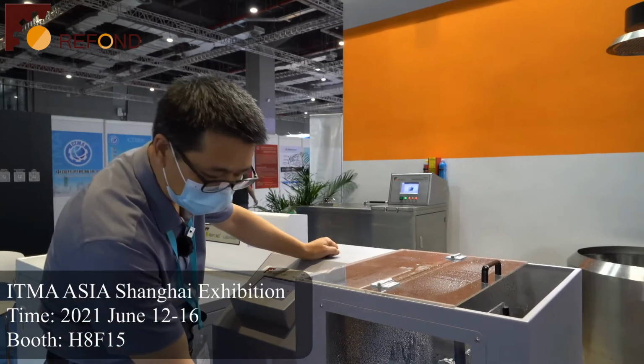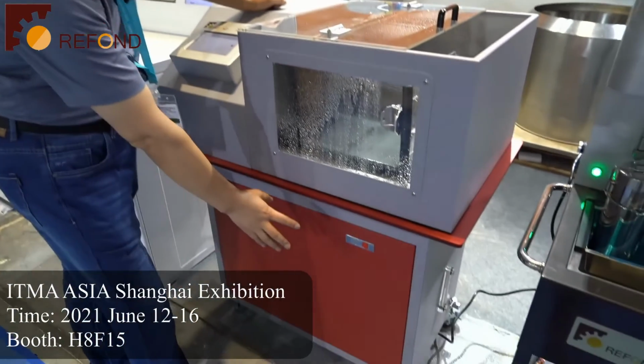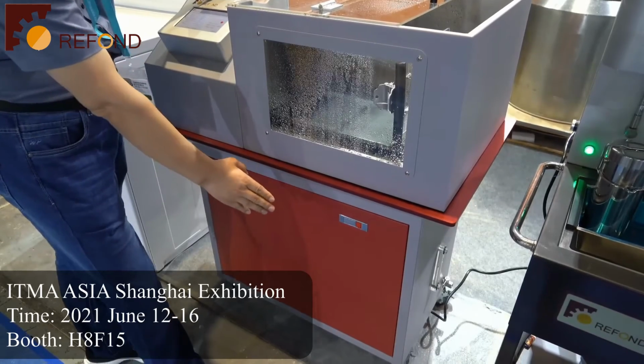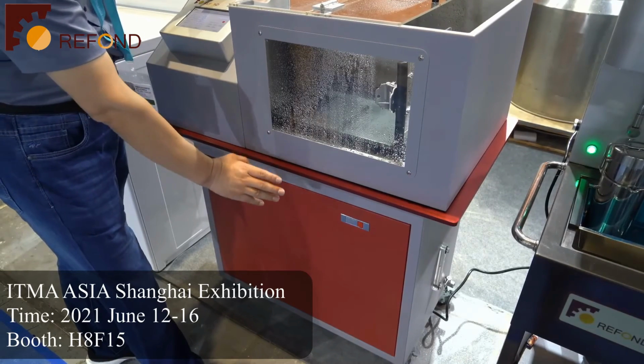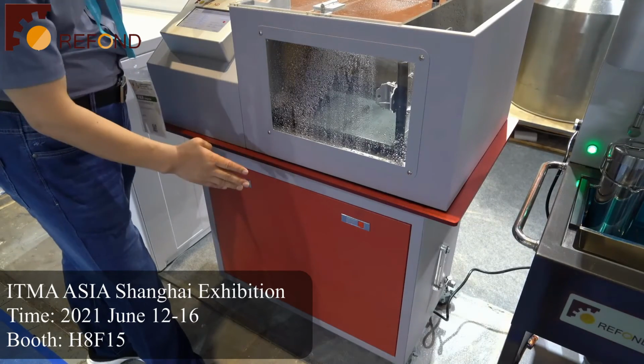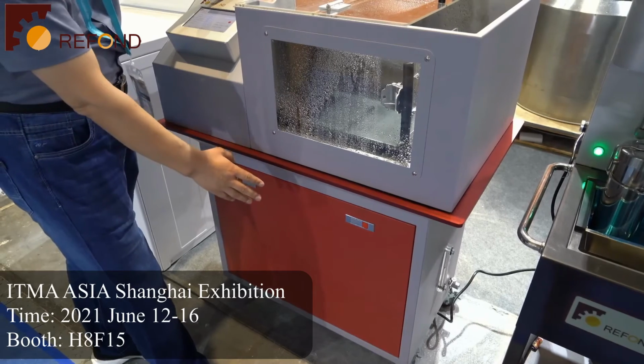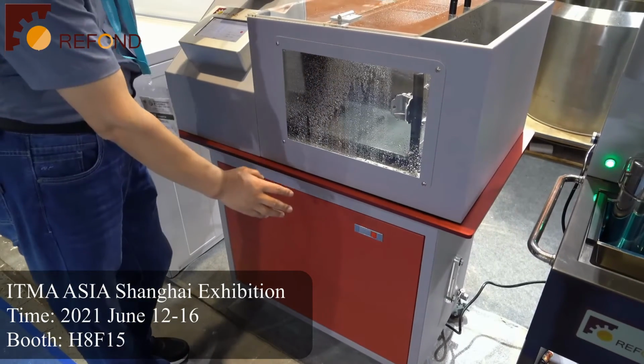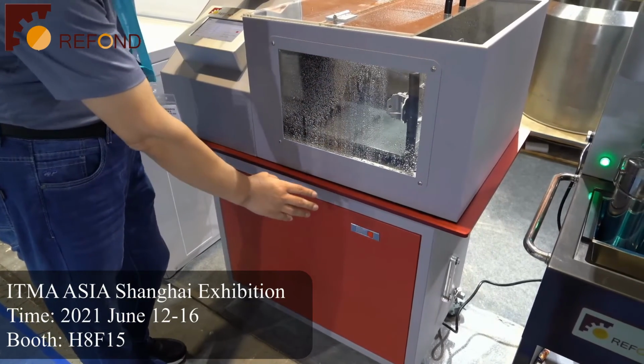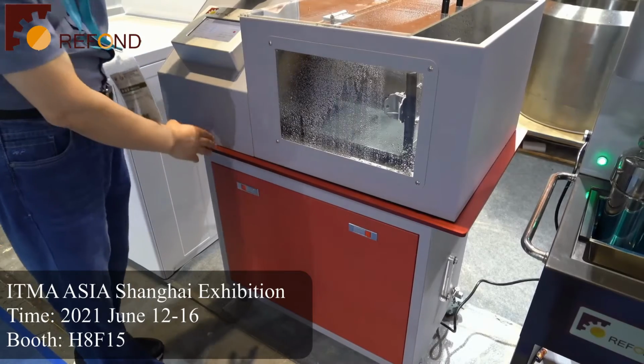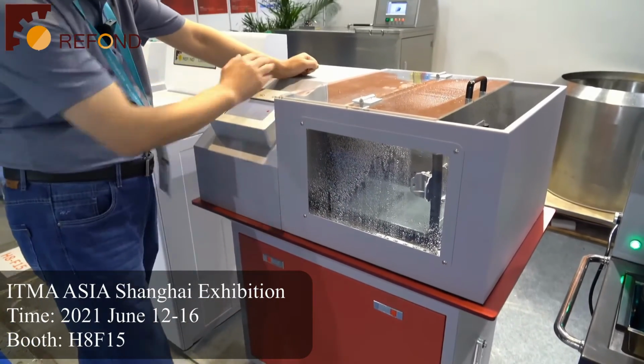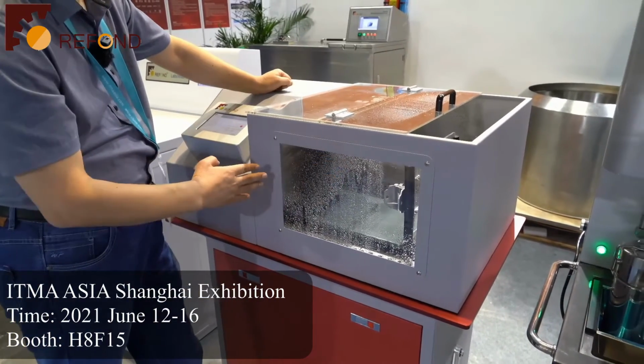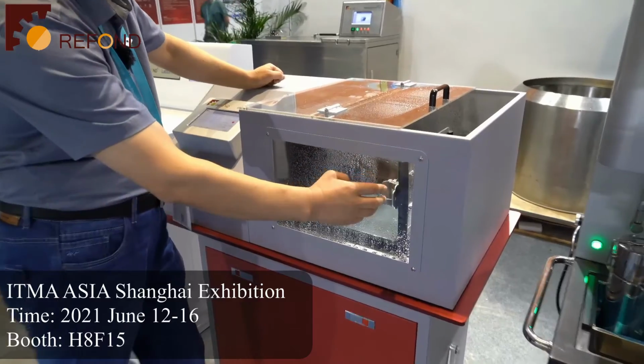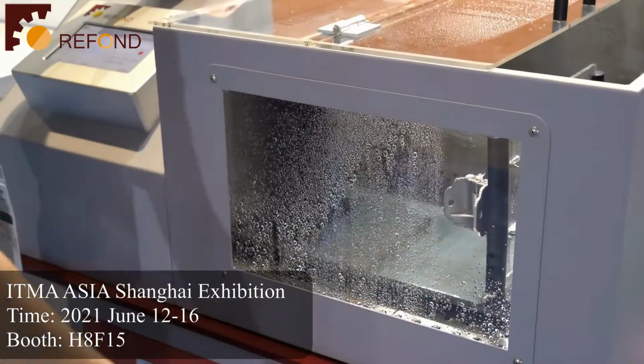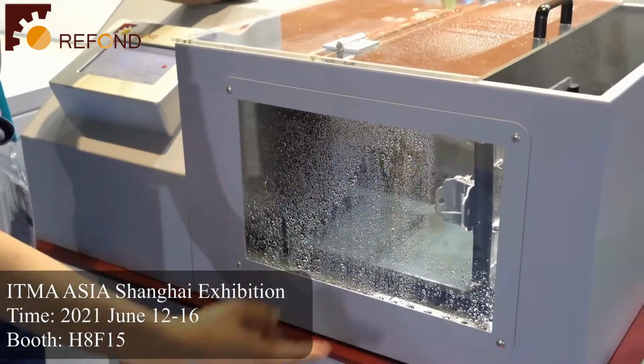The water tank is at the bottom of the machine, and they have the water level control. They have the water heater inside the water tank. They can control the water temperature. They have a water pump which can pump the water to the outside, then spray water to the specimens to form a circulation system.